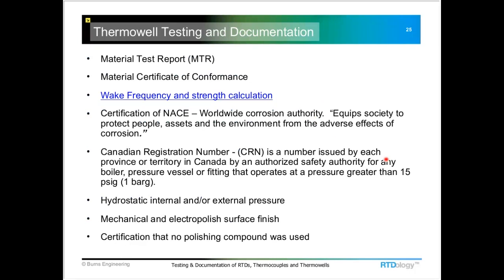Some of the other testing that can be done with thermowells and certifications, there's this NACE, which is a kind of a corrosion authority, and a Canadian registration number. In Canada, it's just a way to track things that are used in pressure vessels over 15 psi. So there's hydrostatic tests.